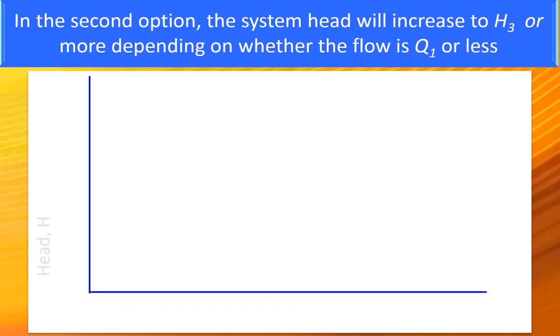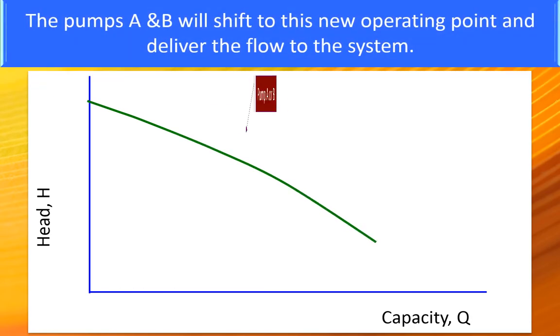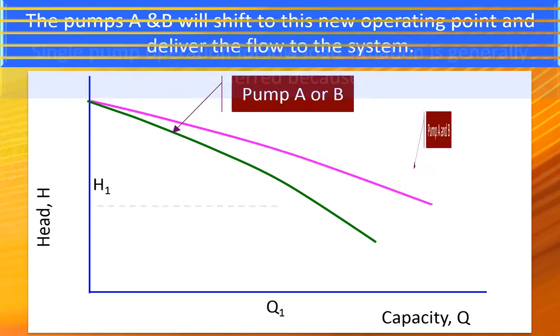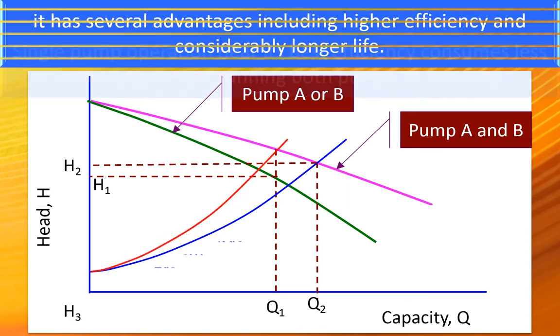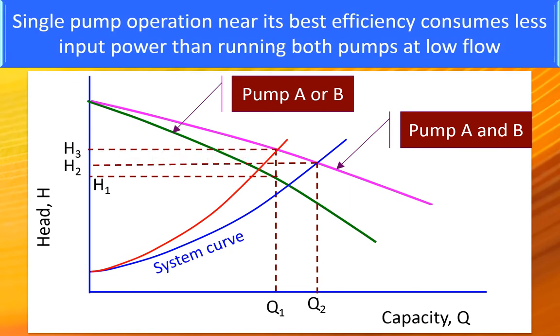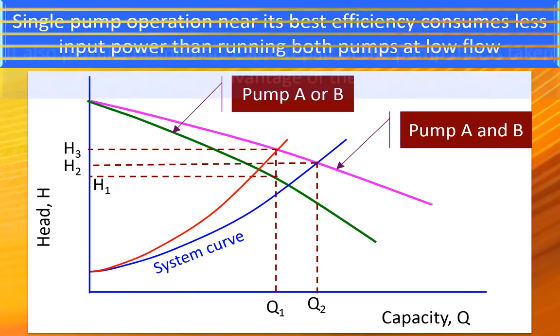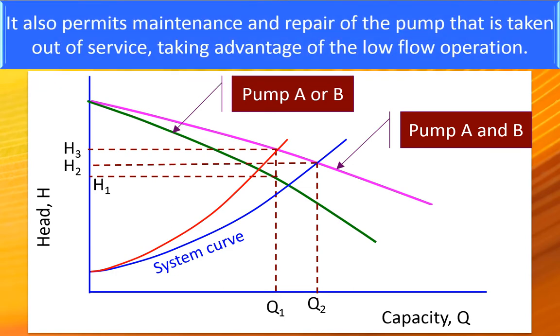In the second option, the system head will increase to H3 or more depending on whether the flow is Q1 or less. The pumps A and B will shift to this new operating point and deliver the flow to the system. Single pump operation for low load situation is generally preferred because it has several advantages including higher efficiency and considerable longer life. Single pump operation near its best efficiency consumes less input power than running both pumps at low flow. It also permits maintenance and repair of the pump that is taken out of service, taking advantage of the low flow operation.